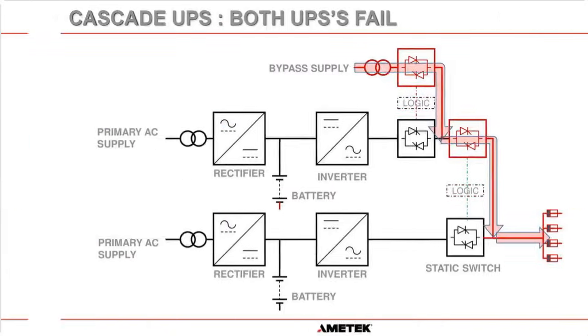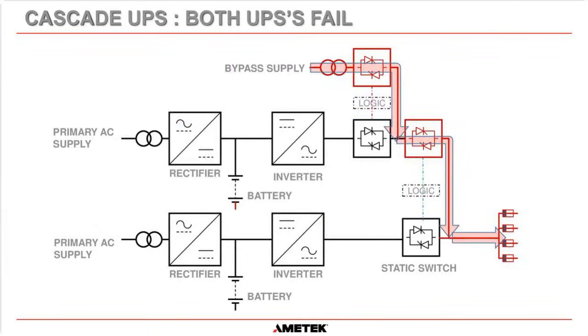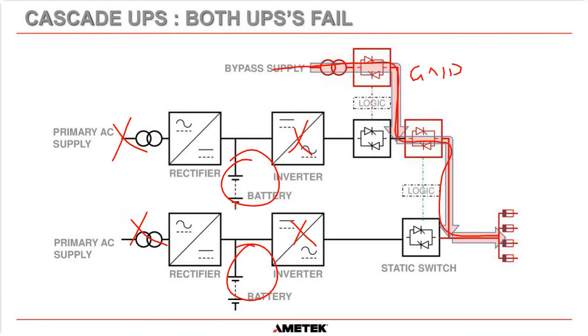And only when that battery has failed, if we had an AC output there, and both inverters turn off, only then will we go to bypass, which is grid power, and it is now unregulated, and it is not smooth AC. It's whatever the grid is supplying you at the time.